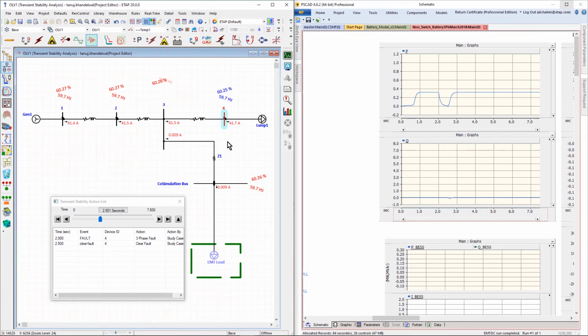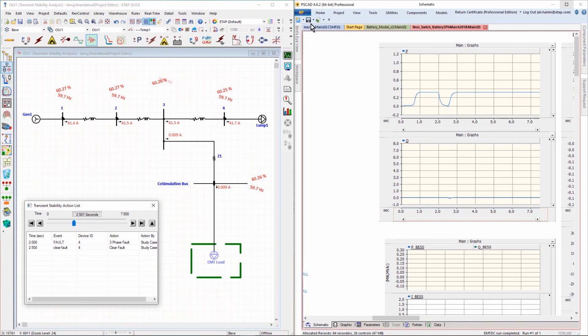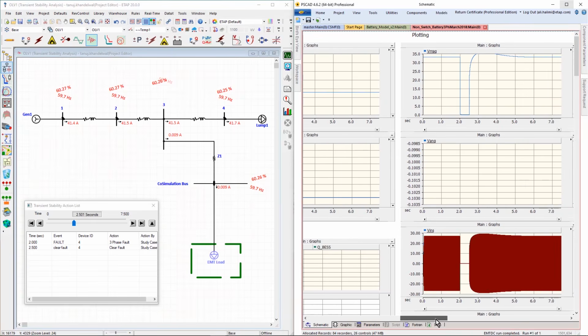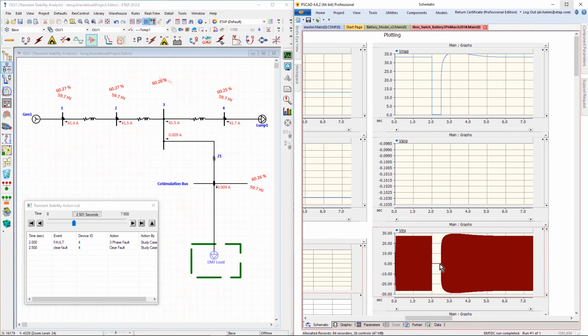So with this technique of co-simulation, you can use ETAP transient stability co-simulating with PSCAD, where you can solve the instantaneous values per phase in microsecond step, and include them in the ETAP transient stability simulation in 0.1 millisecond step. So you end up including the entire power electronics behavior as part of the complete network simulation.